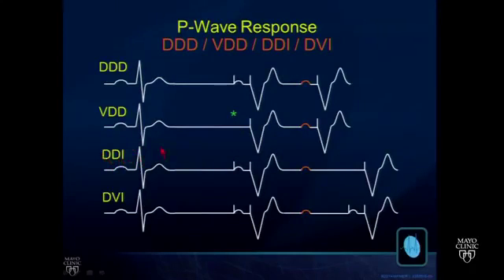DDI is just fixed rate backup dual chamber pacing. So we don't have the capacity to have triggered pacing after an early P wave. We inhibit in response to that P wave in the atrial channel and pace the ventricle at the end of the minimum pacing rate cycle length. Same thing for DVI, which is now just of historical interest, but we only sense in the ventricle, so we can't respond to that P wave, and we'll pace the atrium. So this slide summarizes the different P wave responses in dual chamber systems and illustrates the concept of triggered ventricular pacing seen only in DDD and VDD.